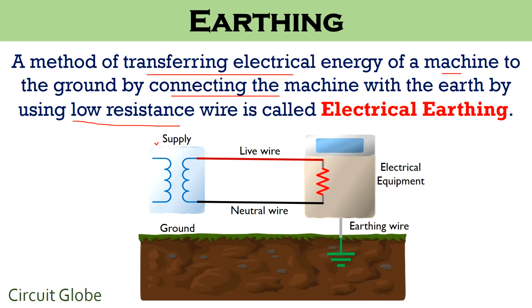So this is our source supply from where external voltage is provided to this electrical equipment, by which current flows through it. Here we can clearly see that electrical earthing is provided to this equipment using this low resistance wire. This is known as the earth cable or earthing cable and provides a low resistance path for the leakage current to reach the ground. Guys, within the earth surface, at this particular position, an earth plate is present. This plate is known as the earth electrode, which is a crucial element of the electrical earthing system.